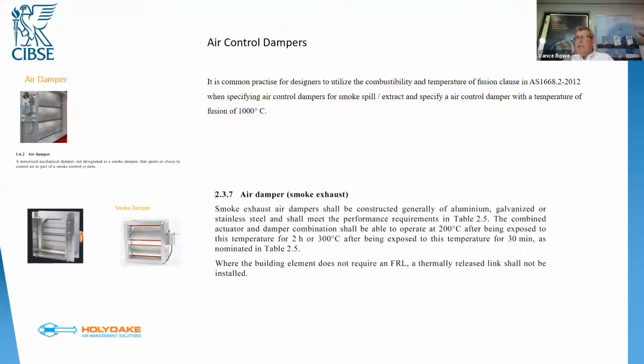Now, air dampers for smoke exhaust are actually listed under the performance requirements in 1682 as being required to withstand a temperature for 2 hours. So that temperature being either 200 degrees C for a sprinkler controlled building or 300 degrees C for a non-sprinkler controlled building. The interesting issue with that statement in 1682 is that there is not an Australian standard test for that criteria. So as a manufacturer, when you take your damper to the Registered Testing Authority, we cannot get a certification to an Australian standard because there is not a testing procedure or procedural standard in existence in Australia currently.